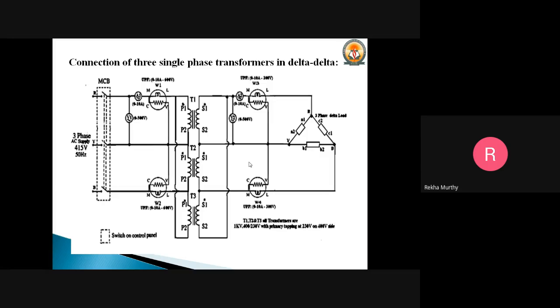In the delta to delta connection, primary and secondary of all the transformers in a bank of three single phase transformers will be connected in delta fashion. This arrangement is mainly used in a system where it is going to carry large currents at low voltages. This is mainly employed at the substation end of the transmission lines, where the main use of this connection is to step down the voltage. From primary you get some voltage, and by the time it reaches the secondary side it gets stepped down, but you will have a large current. That is what you see in the delta to delta connection.